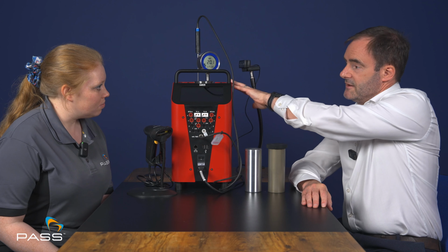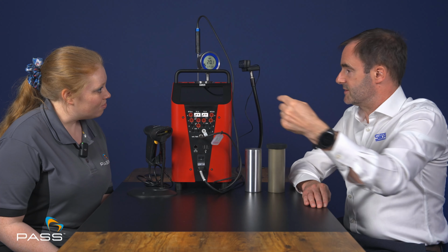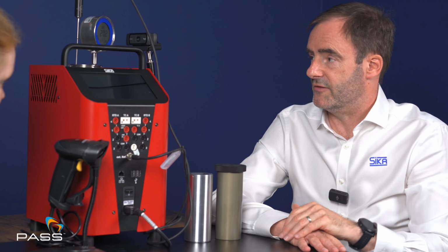On top of that, we have another block where we can do surface temperature. So we have a surface temperature block, which would drop into, again, the calibrator. The temperature sensor would sit on top, and the reference sensor would go directly underneath the device under test, and then we'll calibrate from there.